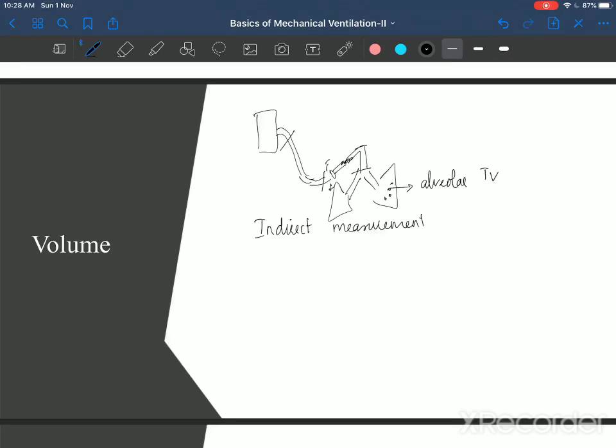Measuring your volume at the proximal airway will eliminate most of the circuit compliance and other dead space factors, but placing a machine there at the endotracheal tube or the patient's airway again creates a dead space, correct? It is also added weight, and this added weight can dislodge the ET tube, resulting in accidental extubation, and suctioning and all will become difficult. So that's the problem with volumes.